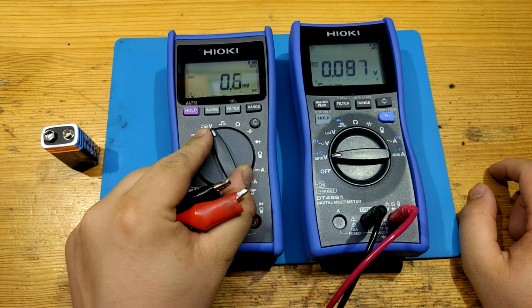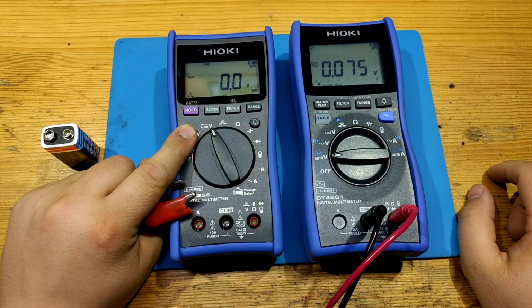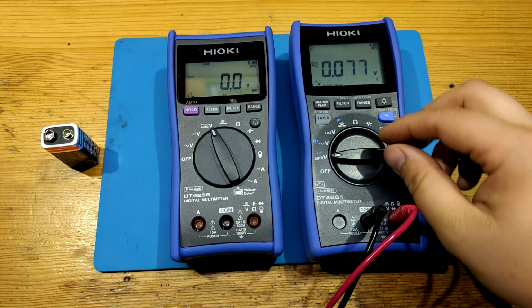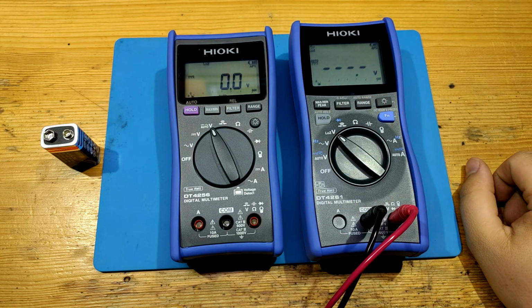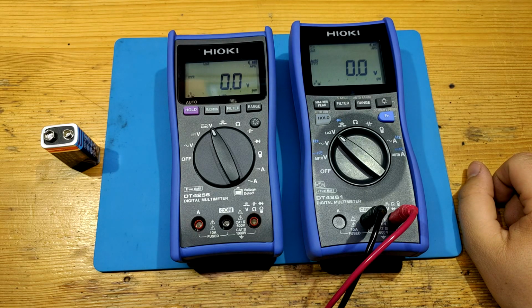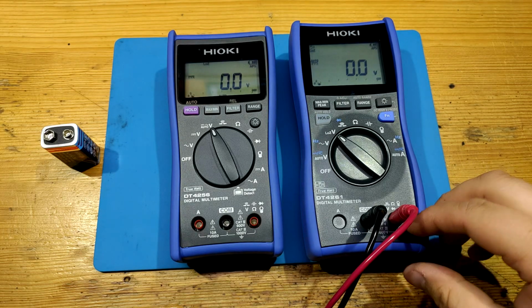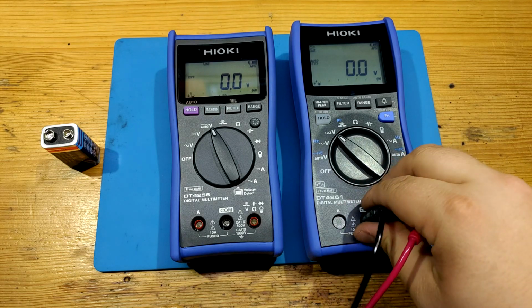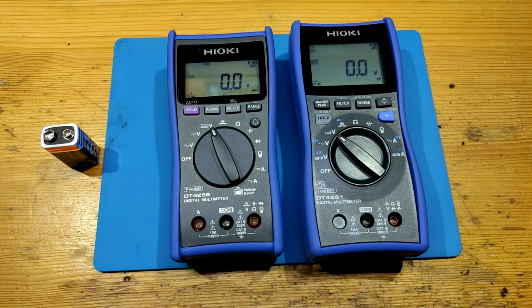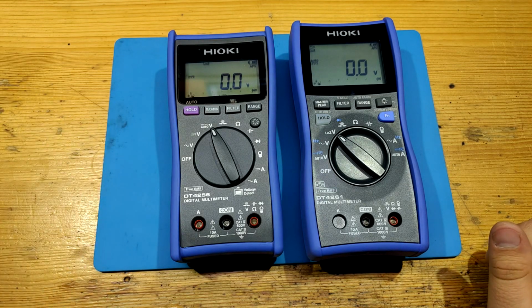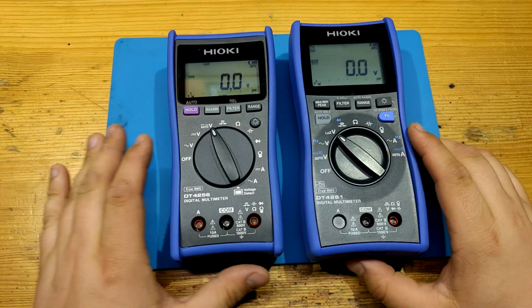4256 has low Z under automatic mode, while 4261 has a dedicated position for low Z. In low Z mode the impedance drops from 11 megaohms to 1 megaohm, so it loads the line a little, eating some capacitive mass. A very useful function if you probe around at least some 10 meters long lines. Personally I would prefer 300 kilohms rather than 1 megaohm, but it's still okay.